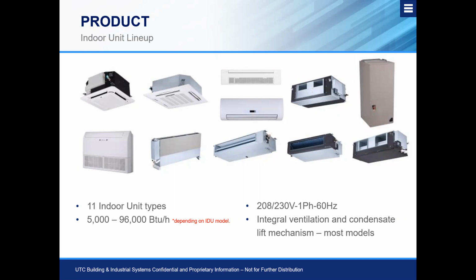We have our one-way cassette, which we see right here above our high wall unit, which is a new product, which we'll get into on the slide to talk about. We have a traditional high wall style unit, which most people are familiar with. We have an outside air processing unit, which essentially is going to act like the DOAS, so to speak. Again, take it with a grain of salt. A good rule of thumb is when we're introducing outside air to this, outside air must be pre-treated and brought up to at least 32 degrees during the wintertime, especially in the Pittsburgh area, because it can get quite cold. You need to make sure that air is pre-treated. But essentially, this acts like a makeup air unit where we're bringing in nice neutral air to the space to meet local constraints. We have a vertical air handling unit, which also has backup electric heat options.